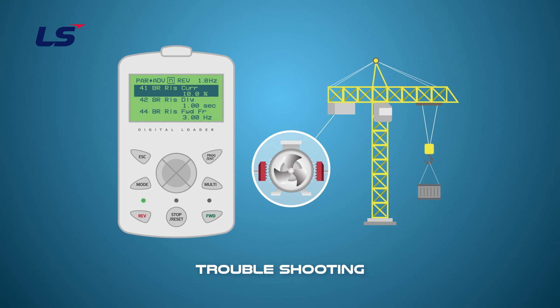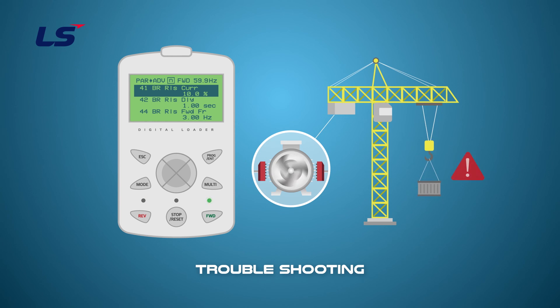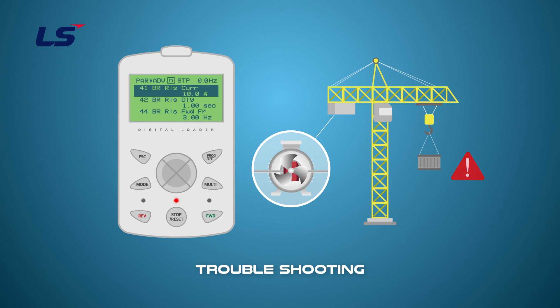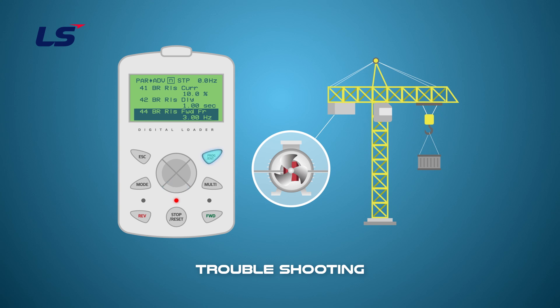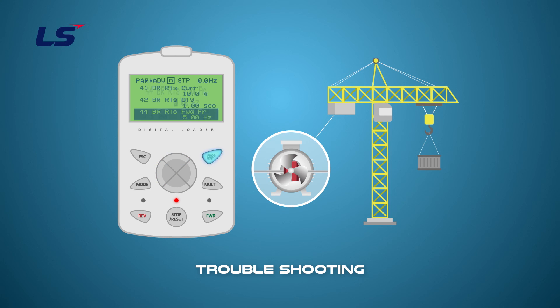Also, there may be situations when the load comes down momentarily and then goes up. This situation occurs when there are large loads operating with not enough torque. In this case, increase the opening frequency slightly to allow starting after achieving enough torque.